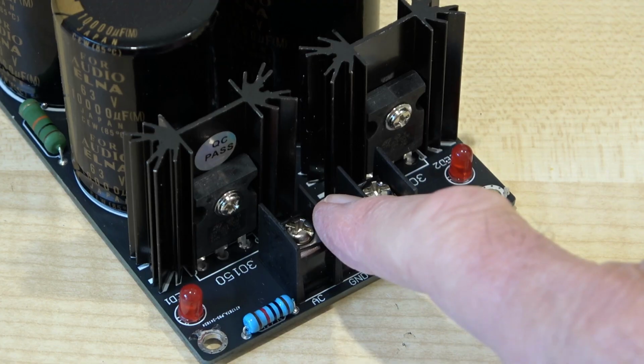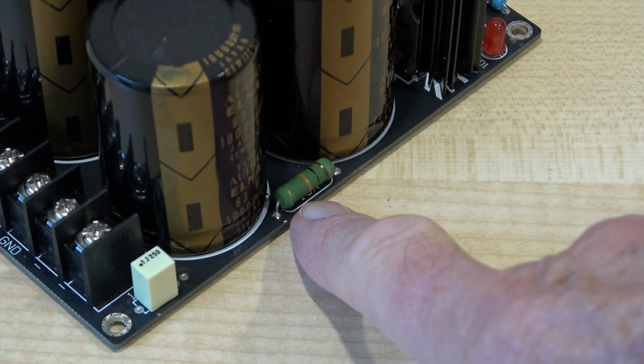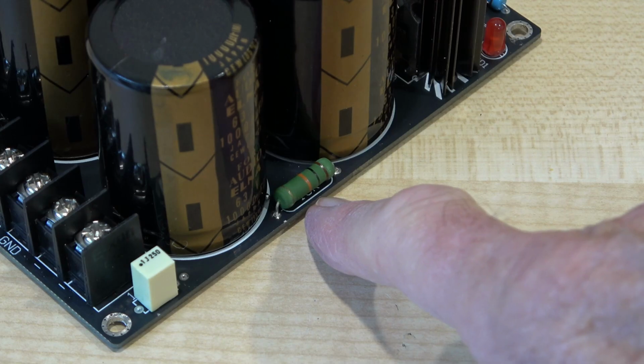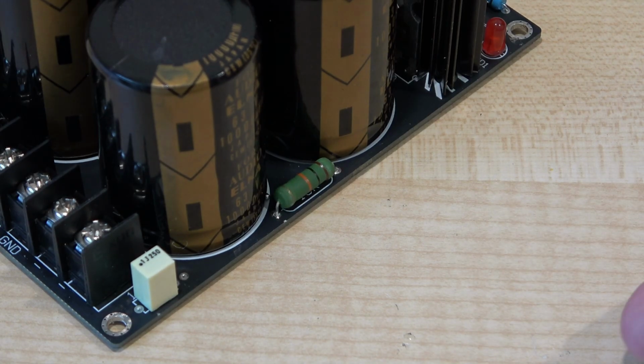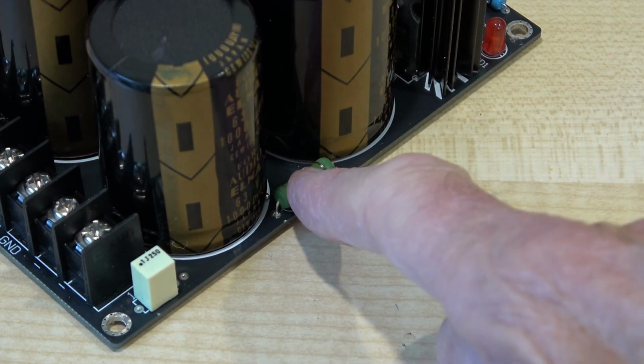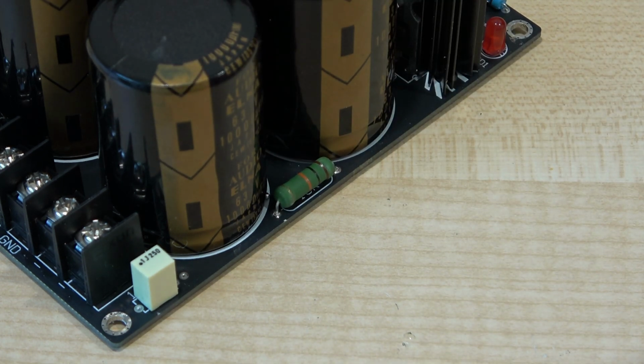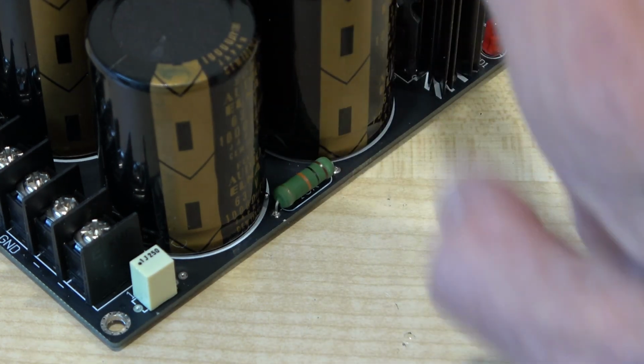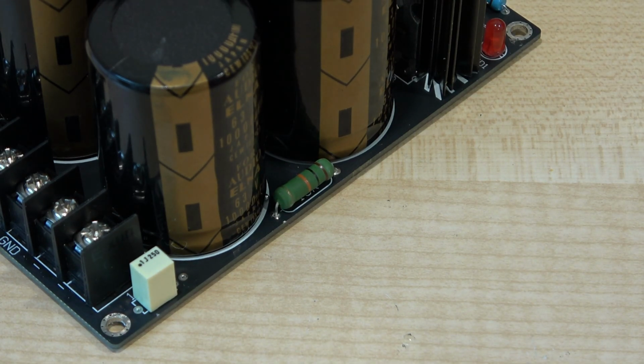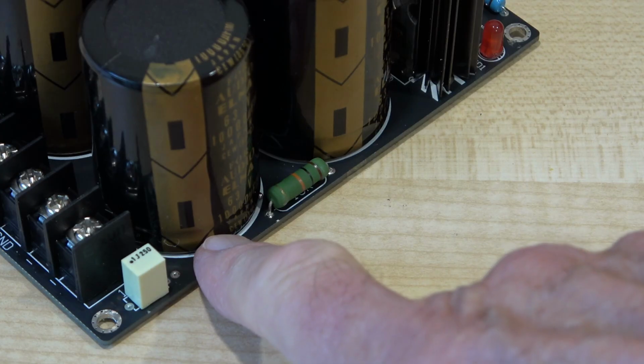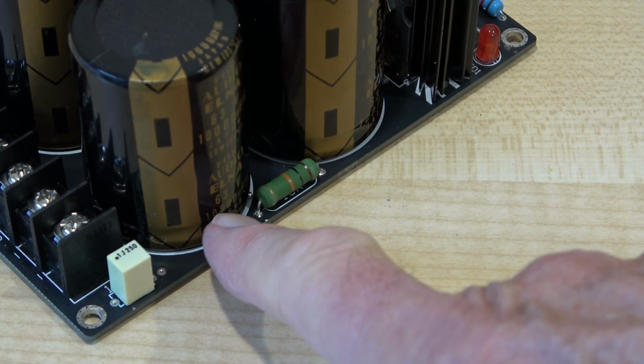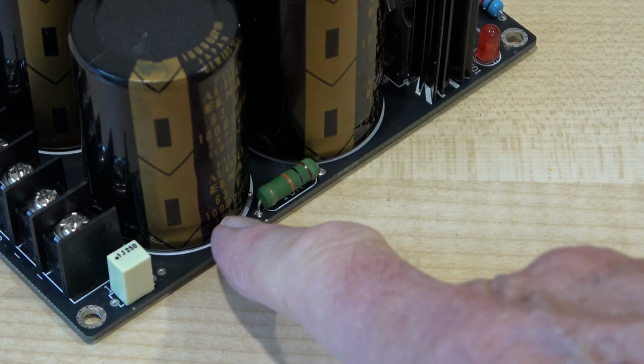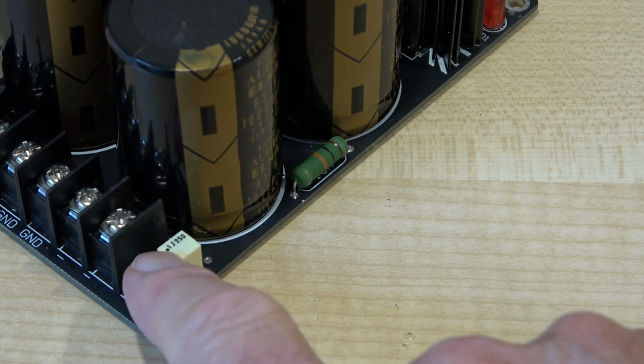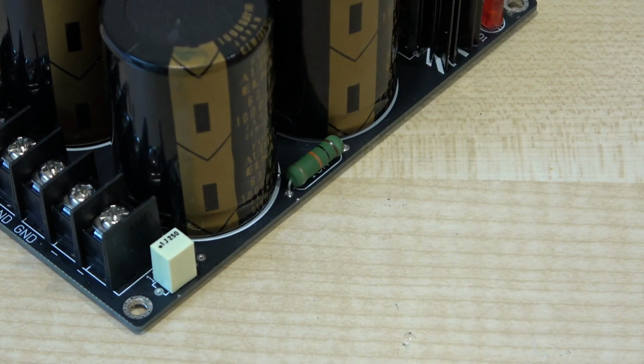Here are your inputs. This resistor, and the same one on the other side, is a bleed resistor. It's across the supply, so if you turn the power supply off with no load on it, these will slowly discharge the capacitors, but they do stay charged as a warning for probably 20 or so minutes. So don't get your screwdrivers anywhere near these capacitors, because you will just blow the screwdriver to pieces. There's also a small cap across the main capacitors, which is a common thing these days.